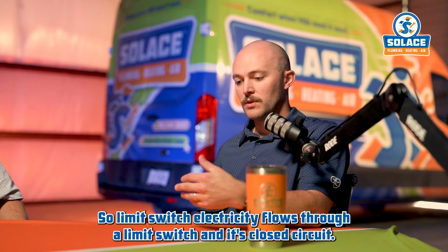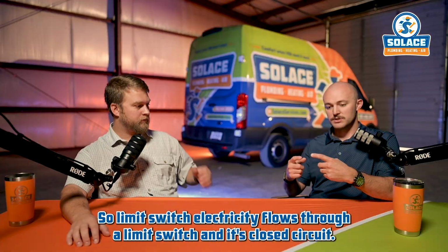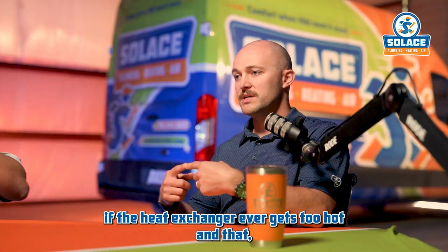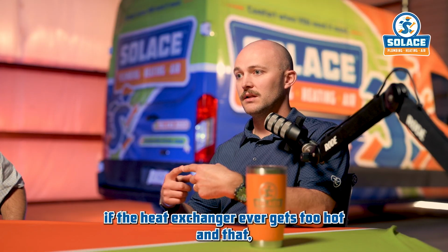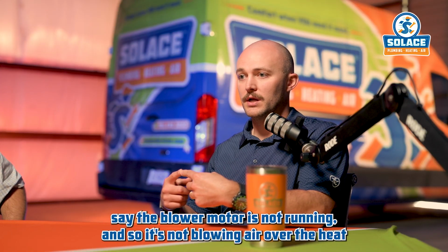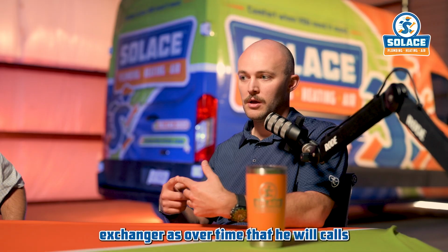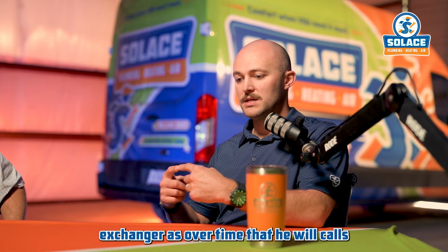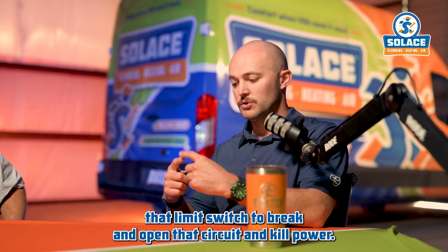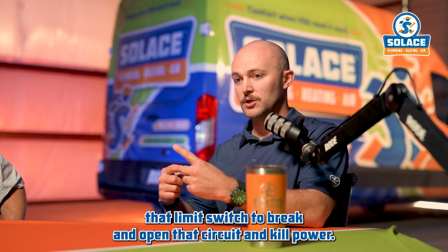So a limit switch, electricity flows through it and it's a closed circuit. If the heat exchanger ever gets too hot, let's say the blower motor is not running and so it's not blowing air over the heat exchanger, over time that heat will cause that limit switch to break, open that circuit, and kill power.